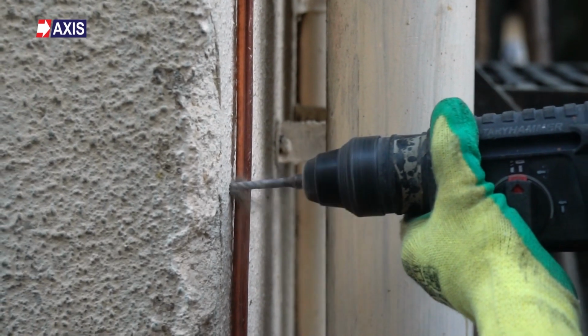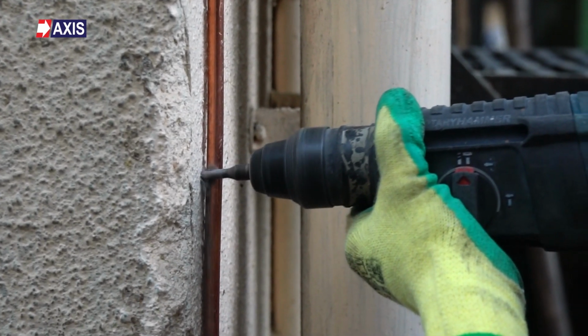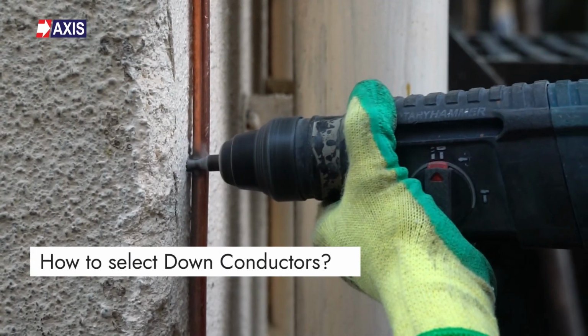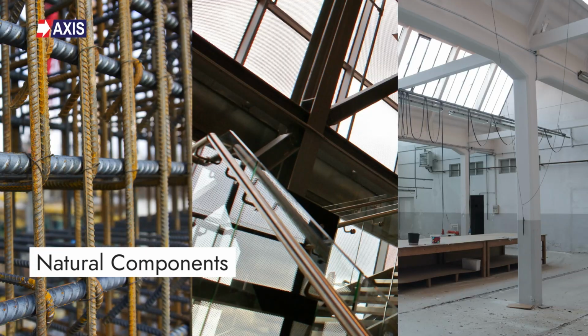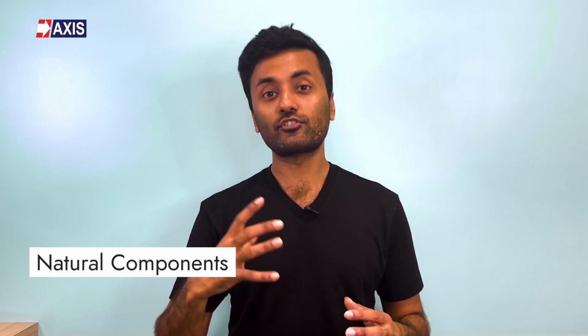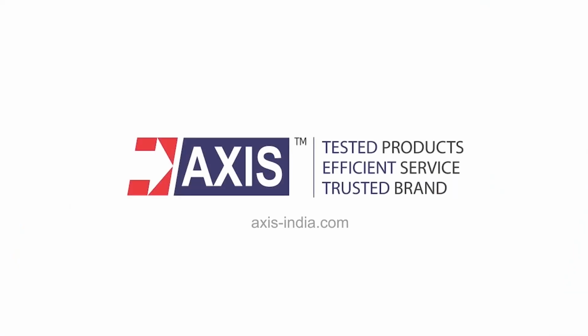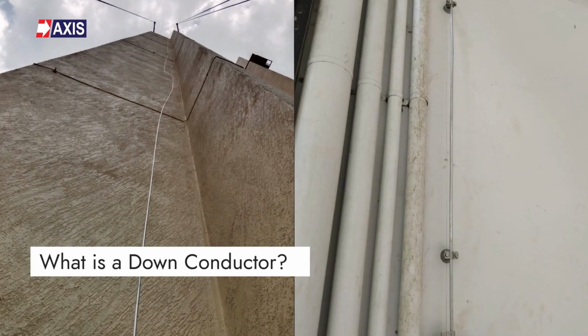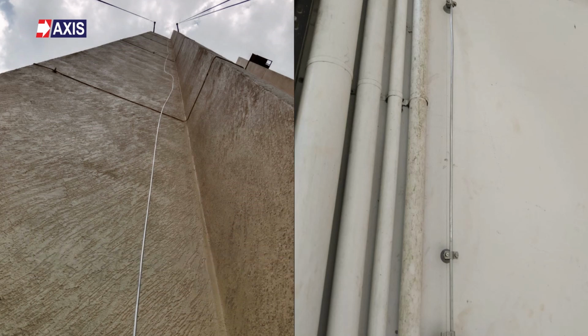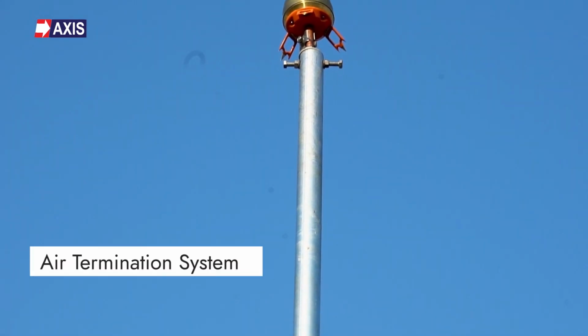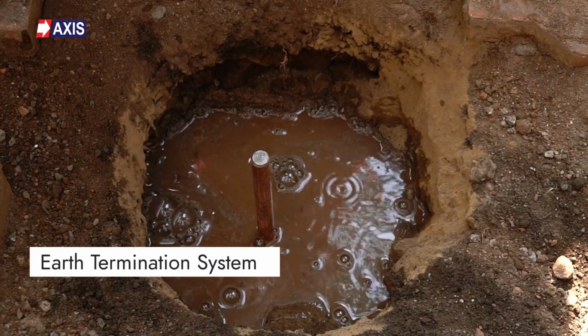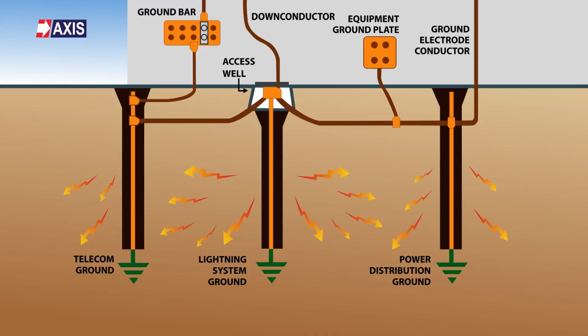After this video, you will have a clear picture on how to select a down conductor for your lightning protection system and the natural components that form a part of the lightning protection system. So let's start by understanding the basics. What is a down conductor? The down conductor is the electrically conductive connection between the air termination system and the earth termination system. Its primary purpose is to safely transport intercepted lightning currents to the ground without causing any harmful temperature spikes.